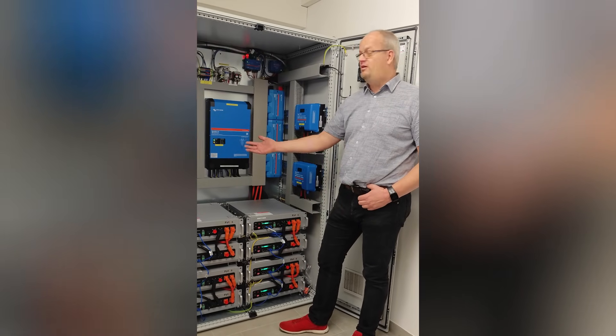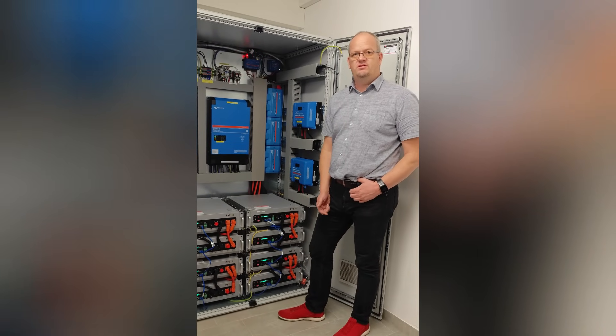The special thing here are the three Quattros — the brothers of the MultiPlus series from Victron — all capable of dual input for both grid and generator power. The installation provides the basic loads of the household and is also capable of transfer switching in less than 20 milliseconds, giving us a total uninterruptible power supply.